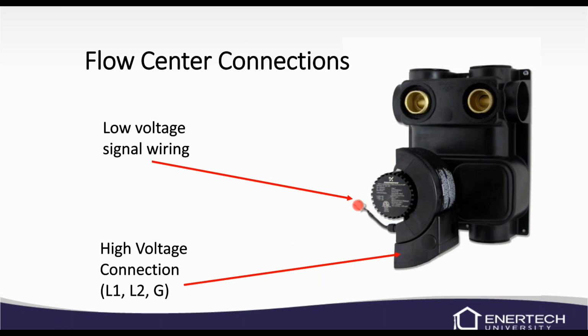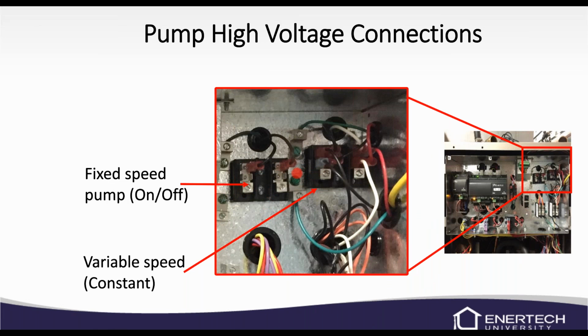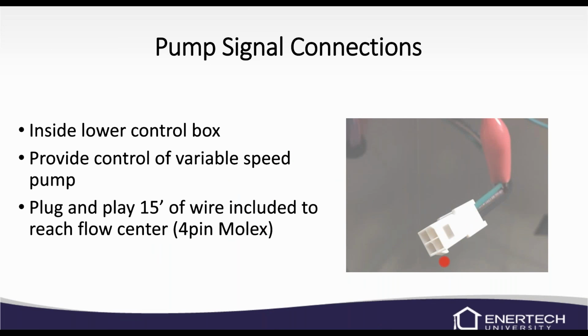Now, this connector that runs from the indoor unit to this connection here is a 15-foot connector. That's a plug and play connector. We give you 15 feet, so in case you need to go up to the ceiling, over and back down, you've got plenty of cable. Again, the pump block for the fixed speed pump has power when the unit tells it to have power. And this is the variable speed pump block, so it will always have 230 volt to it. This is that 4-pin connector. Again, it's a plug and play wire, and there's 15 foot of it. It'll plug right in to the flow center and also to the board in the unit, the pump relay board.